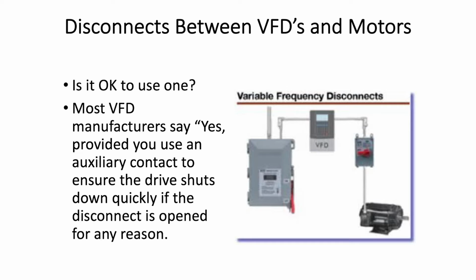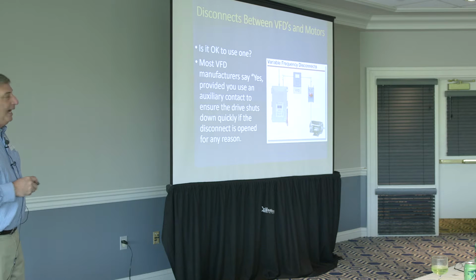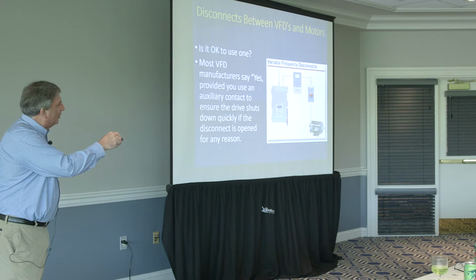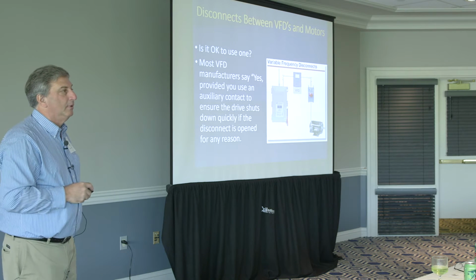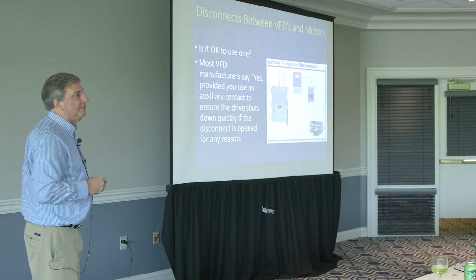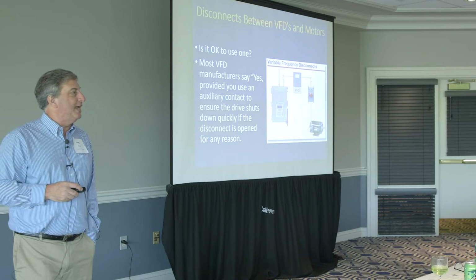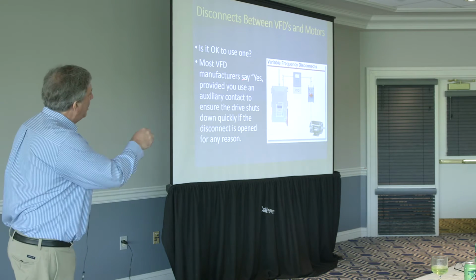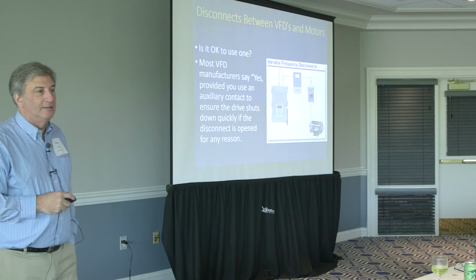Don't have to. Now, the final safety thing for the day, just an FYI, is it okay to use a disconnect here between the VFD and the motor? So, most VFD manufacturers say yes, provided you use an auxiliary contact to ensure that if this device is open to disconnect the motor, the drive is simultaneously shut off. I can't just have a disconnect here that opens the motor and leaves the drive running. And that's relatively new from most of these manufacturers. Many of them have said in the past, no, you can't do that. Or doing that voids the warranty if it's just a disconnect for your drive.